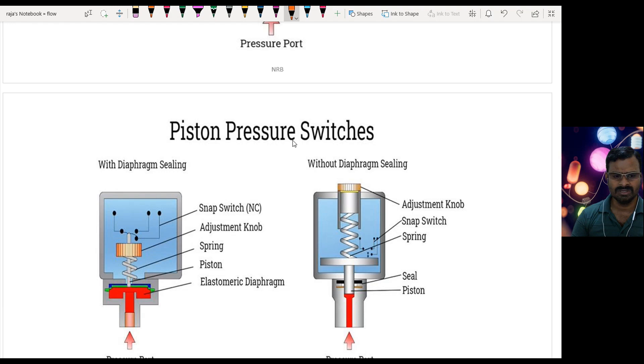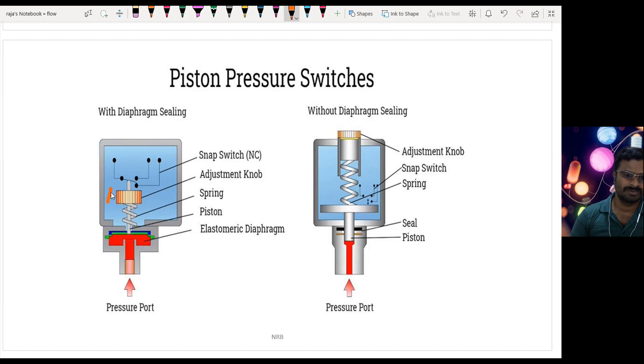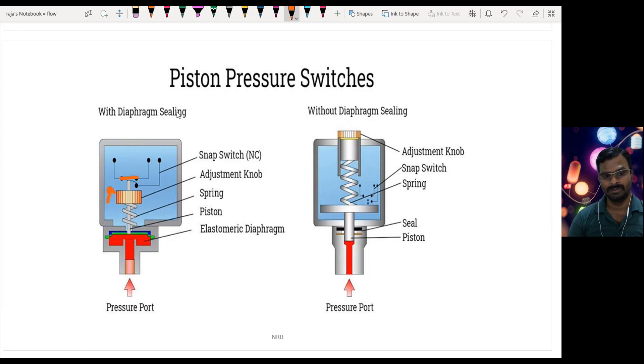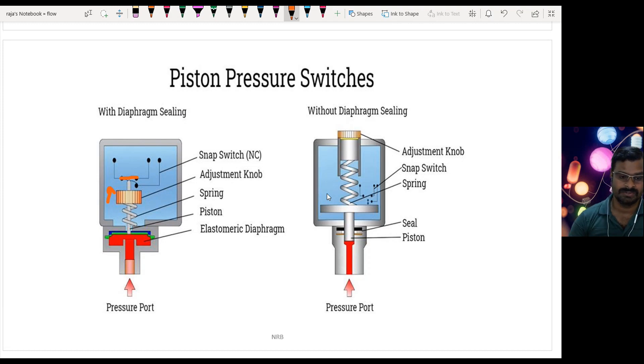The piston type pressure switch has a piston. Liquid is applied against a spring, and when enough pressure is applied the piston pushes the spring and moves upward, making contact from NC to NO so the switch closes and current flows. This signal is given to the PLC. These are the different types of pressure switches mostly used in industry.